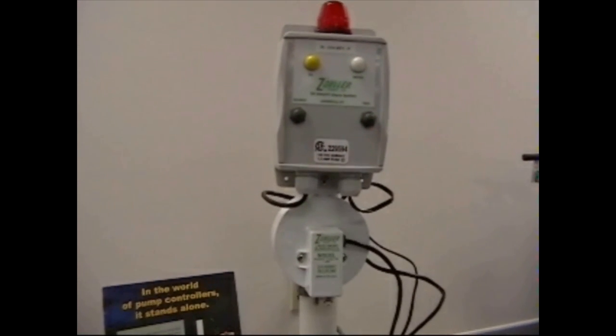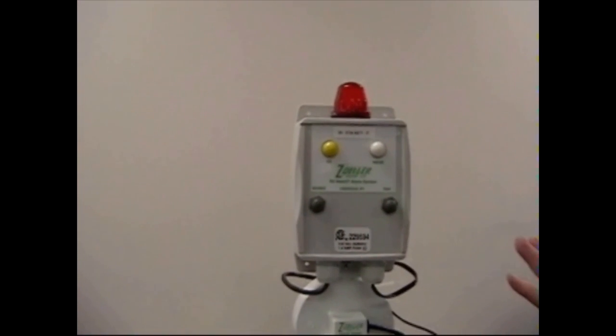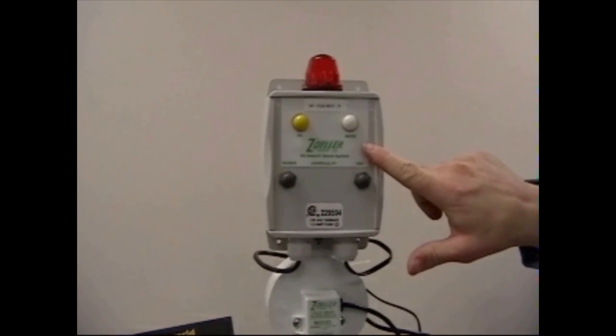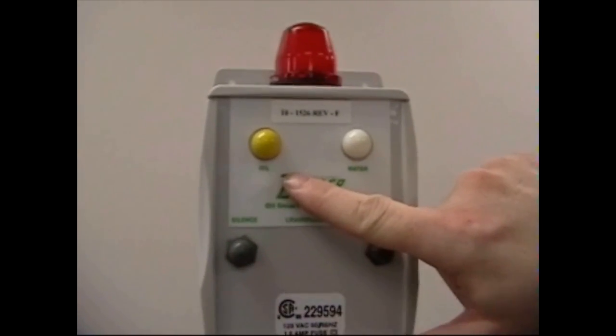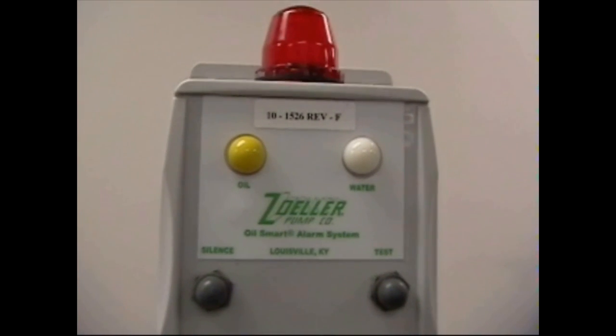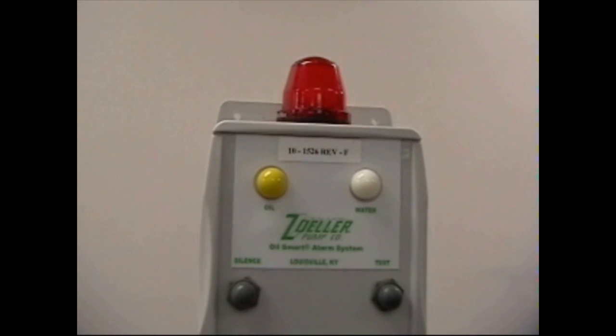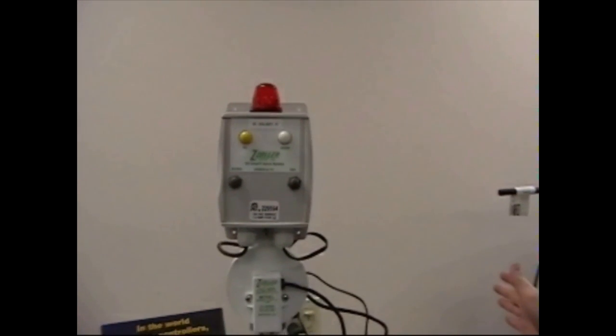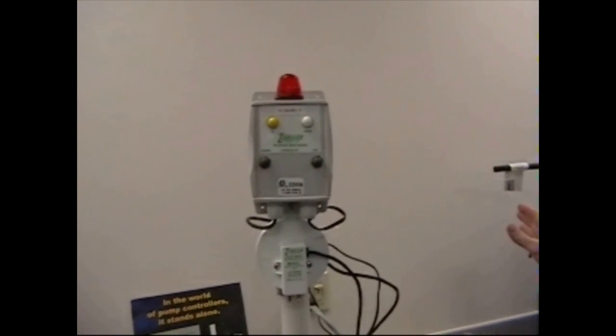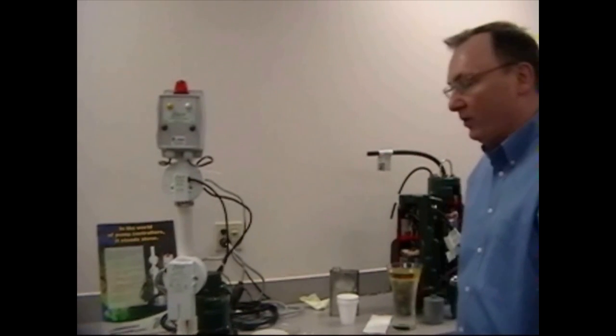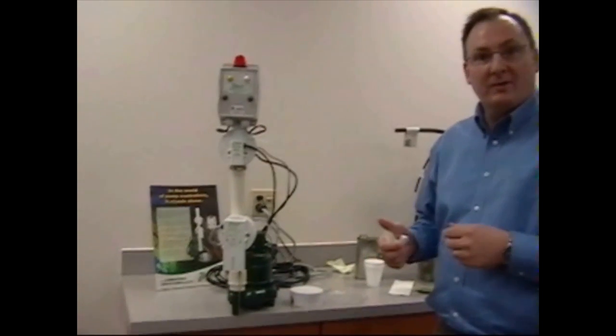The third component of the system is the alarm box. This is a sealed UL listed box that will indicate either if there's a high water condition or a high oil condition. It comes with a test and silence switch, and it also includes dry contacts that allow you to relay that information to a monitoring center so it can be monitored offsite. Those are the three main components of the OilSmart system. Thank you very much.